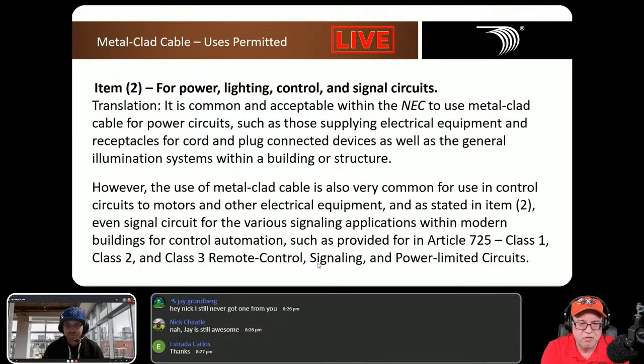There are also applications where signaling circuits are done in MC cable, and some building automation is done in metal-clad cable too. So it's not always just power—it can be power, lighting, control, and a mixture of both. In fact, that's what our MC LED is for Encore Wire, but other companies call it MC PCS or MC Duo. It's a mixture of 0 to 10 volts for lighting and control, plus power conductors, all together in the same assembly.